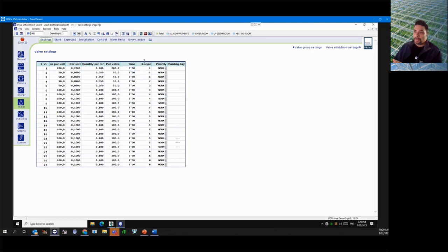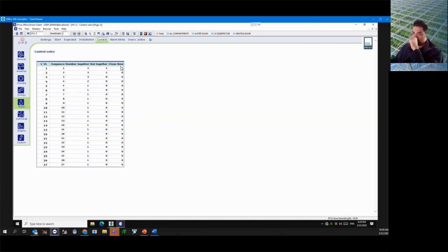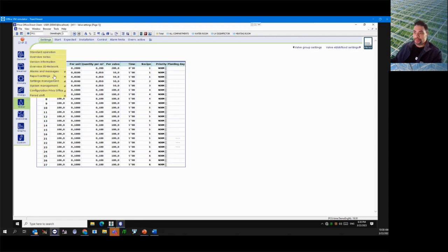Okay. And Jose, sorry to interrupt you. We had a question come through about the earlier discussion. They were asking, so with negative, you will have 2 valves open for a short period of time on the close time? Yes. Okay, thank you for clarifying. Yeah, when it's negative, before the valve that's irrigating closes, the other one will be fully open. Yes. Okay, thank you.